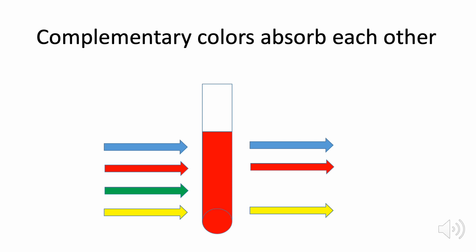So that's why it's very important for you to always remember that if you are performing spectrophotometry, you should have an idea of the final color of the product or the test, because the type of light it will absorb will matter. So, if you're processing a red-colored solution or final product, it's important to set the spectrophotometer within the wavelength of the green light, because that is the type of light or color that is absorbed by the red color.